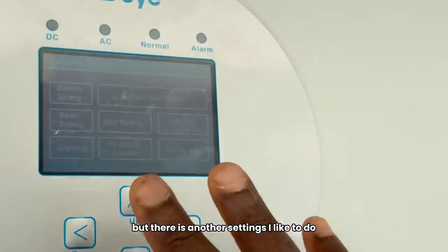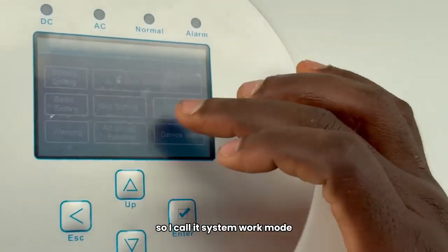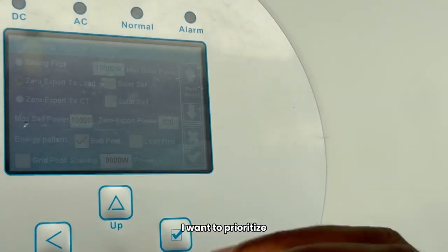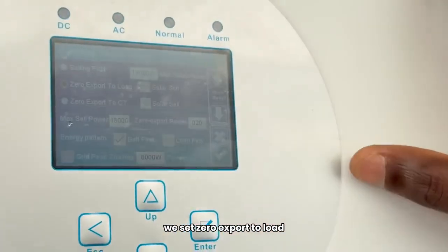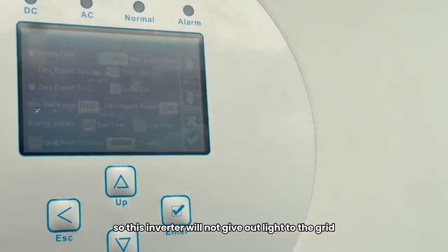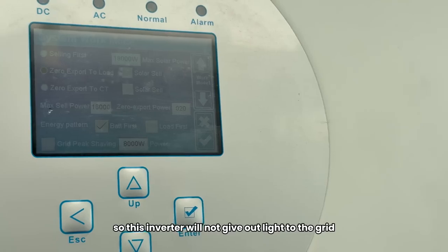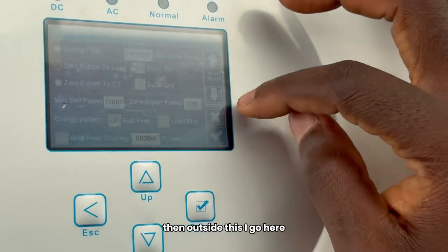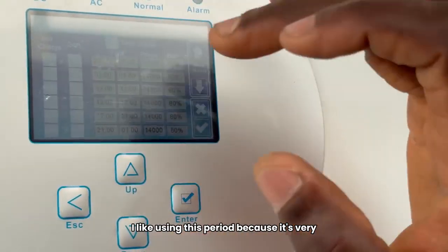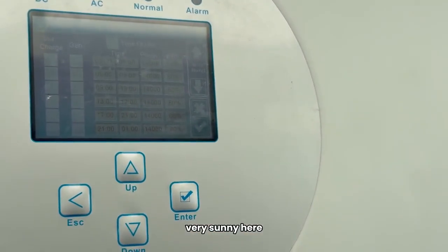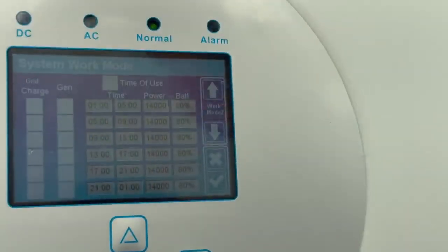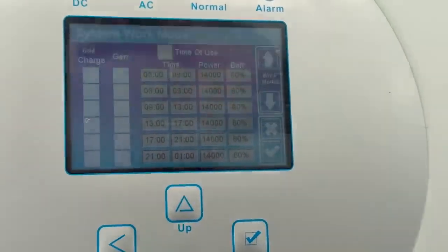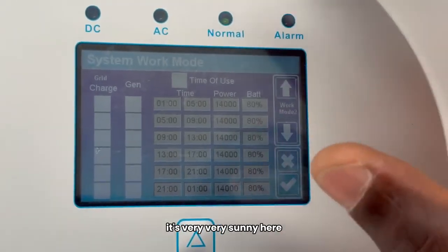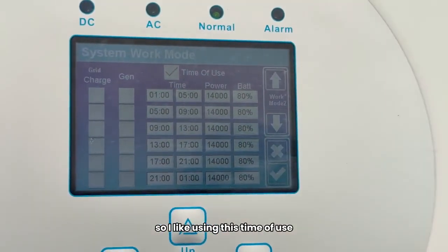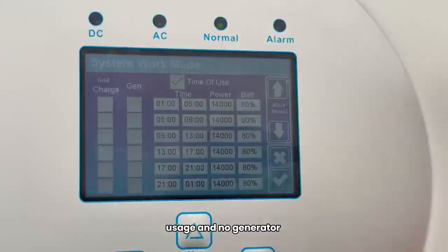But there's another setting I'd like to do, called system work mode. I want to prioritize, so first we set zero export to load, so this inverter will not give out light to the grid. Then outside this, I go here - I like using this period because it's very sunny here. Let's center it at the middle, ignore this.